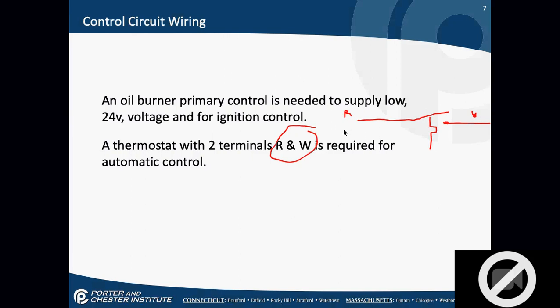Is a thermostat a switch? Yes. So am I going to have any resistance when this is closed? You should. Why? That I couldn't tell you. Oh, come on. What did we talk about yesterday that's in series with the thermostat? The relay coil. There's one small device. I said it's adjustable in a, or we might have talked about it when we talked about thermostats. I said it's adjustable in a heating thermostat. High limit. Nah, that's not going to be with your thermostat. Anybody remember the anticipator?